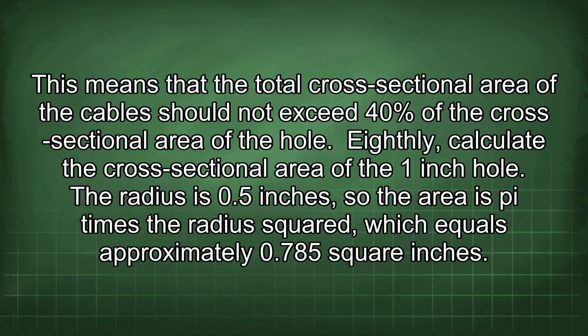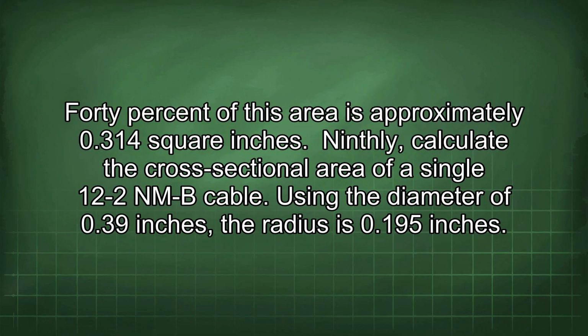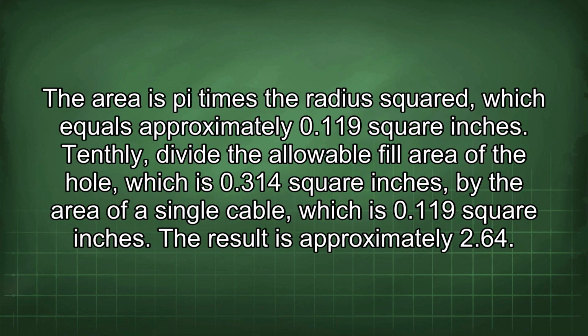The radius is 0.5 inches, so the area is pi times the radius squared, which equals approximately 0.785 square inches. 40% of this area is approximately 0.314 square inches. Ninthly, calculate the cross-sectional area of a single 12-2 NM-B cable. Using the diameter of 0.39 inches, the radius is 0.195 inches. The area is pi times the radius squared, which equals approximately 0.119 square inches.